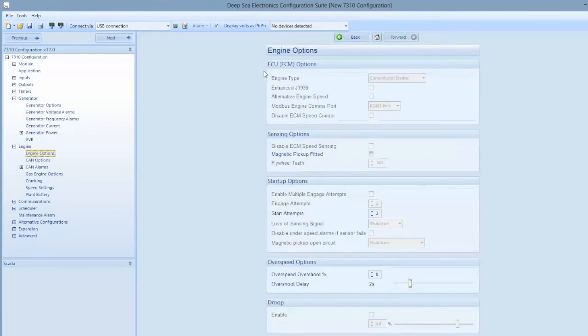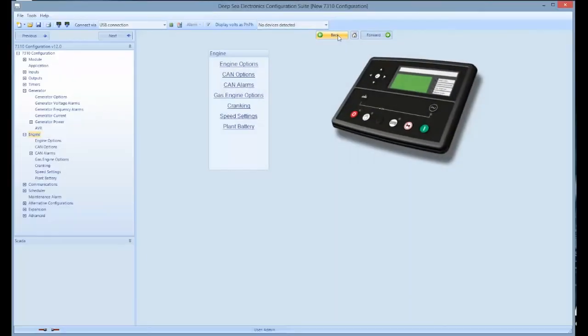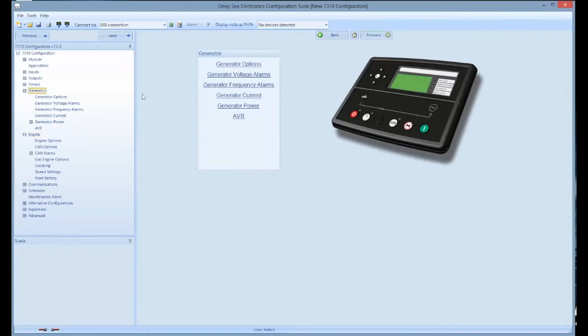Changing the engine parameters will enable the engine to be shut down when outside the parameters of the ECU, but only the engine OEM can reprogram the ECU unit. You do have control of your generator volts, current, and frequency parameters as indicated here by selecting generator on the left hand menu that brings up all the generator settings available.